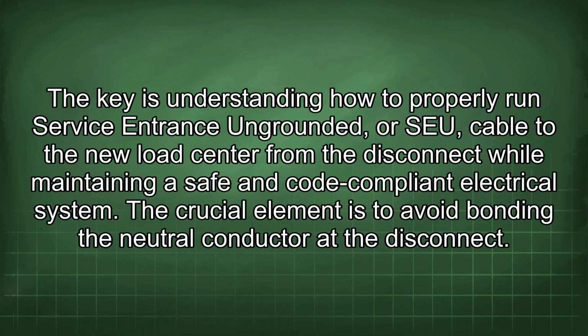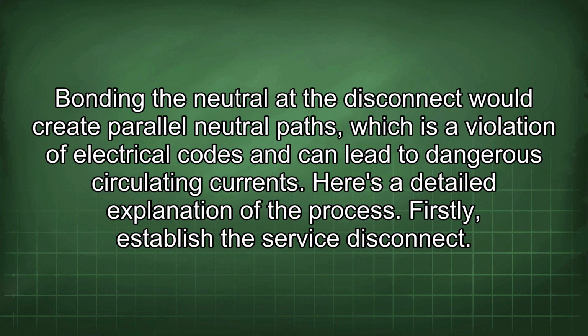The crucial element is to avoid bonding the neutral conductor at the disconnect. Bonding the neutral at the disconnect would create parallel neutral paths, which is a violation of electrical codes and can lead to dangerous circulating currents. Here's a detailed explanation of the process.